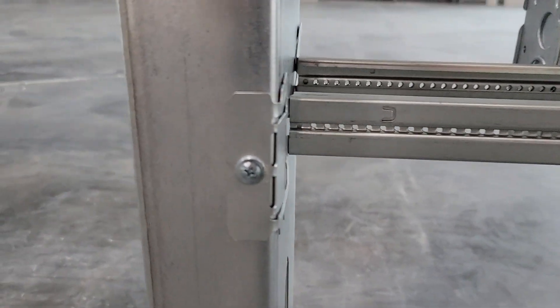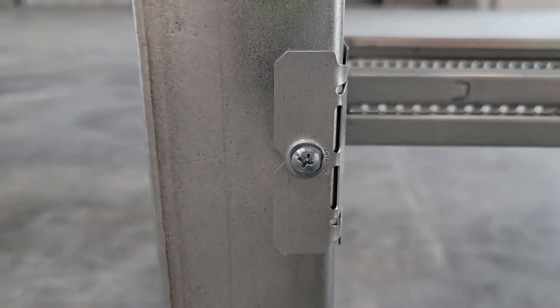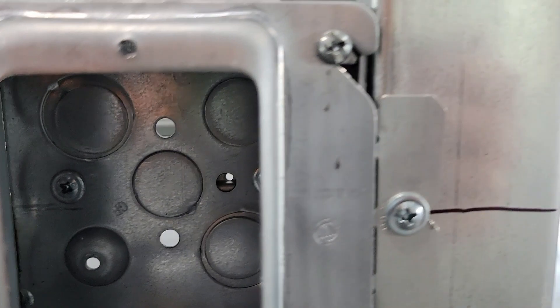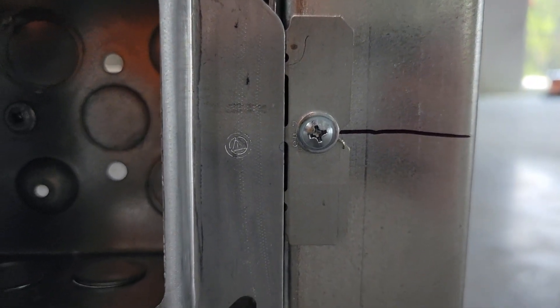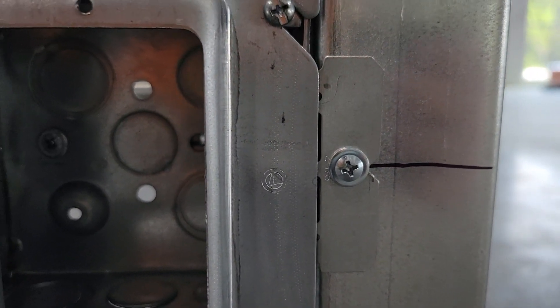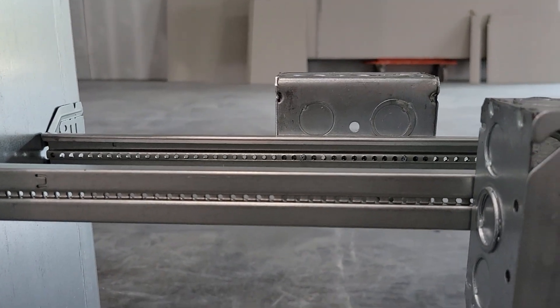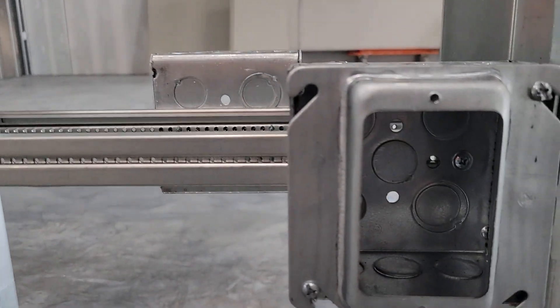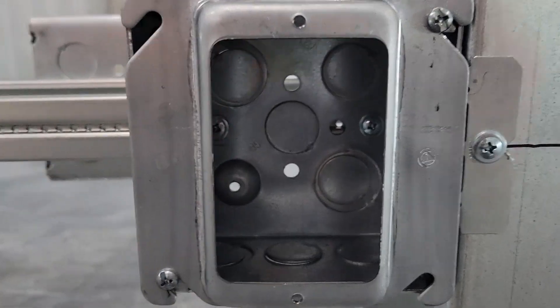Once you get it spread apart, it sits nicely on the lip. Mark your center where you want the center of your box—that's where you put your screw. Then level your bracket, put your box on it, and screw it in.